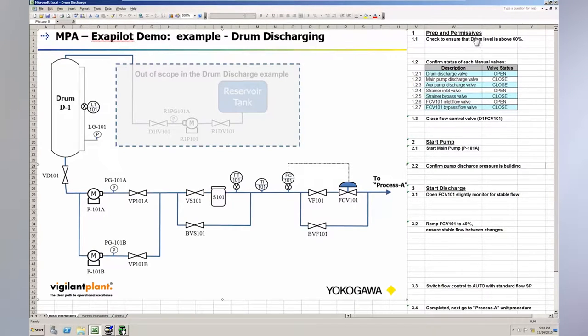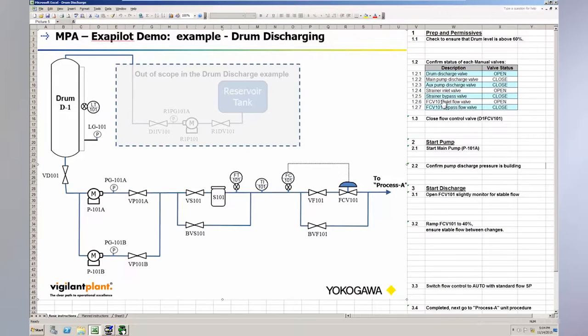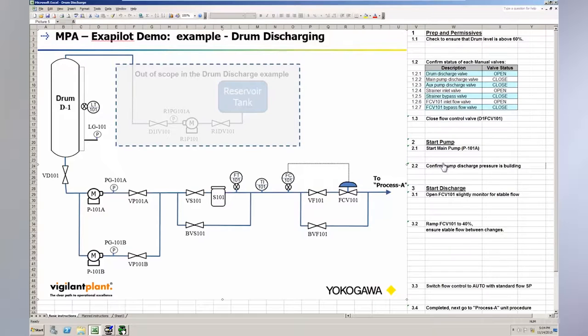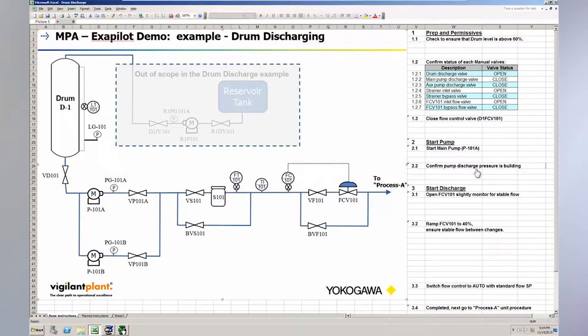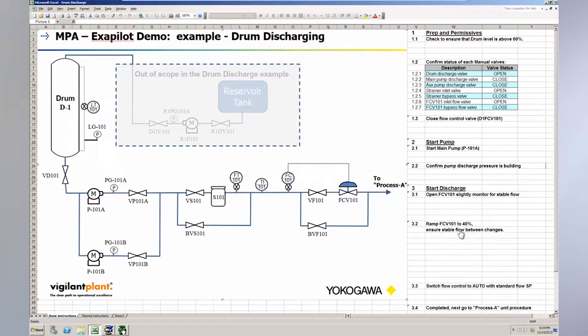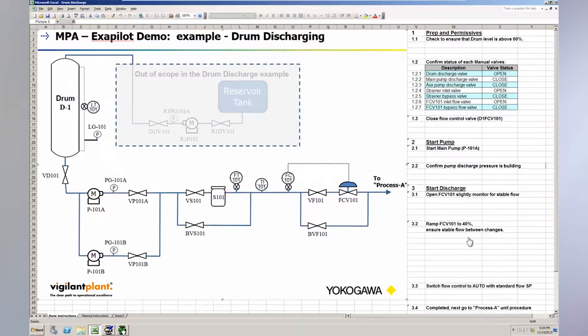First is the Prep and Permissive section. Next is the Start Pump section and lastly we have the Start Discharge section. The Prep and Permissive phase specifies the valve positions and system settings required to perform a safe drum transfer. The Start Up phase calls for the actions of the operator to start up the pump and provides guidelines for monitoring the system for stable pressure and flow conditions. The Discharge section contains a ramping procedure that provides low level guidance within the SOP for ramping the flow.